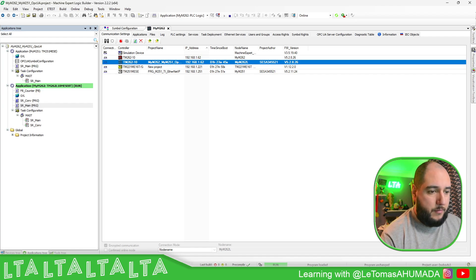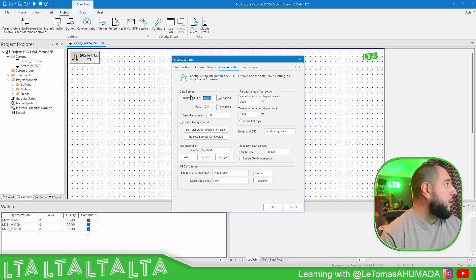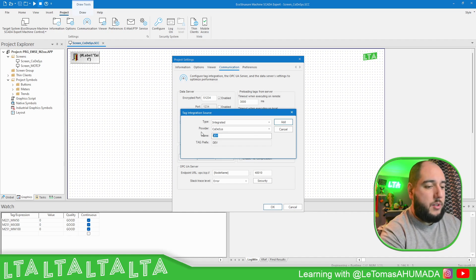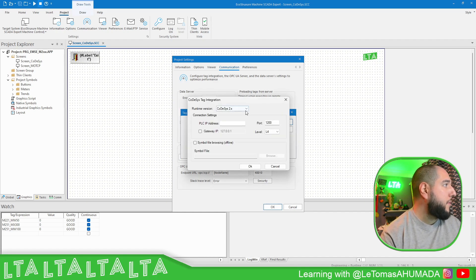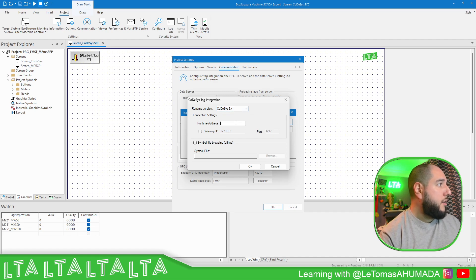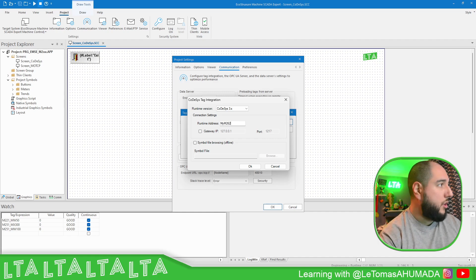Now on the Machine SCADA Expert, just open it. On this side we just need to go to Communication. On the communication side, we just need to add a new source. Here we just need to add CoDeSys — just define the name, it's going to be 'my M262'. Here just define the version: version 3. Runtime is going to be 'my M262'.